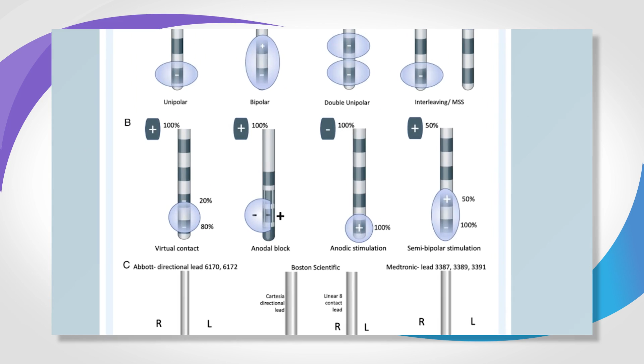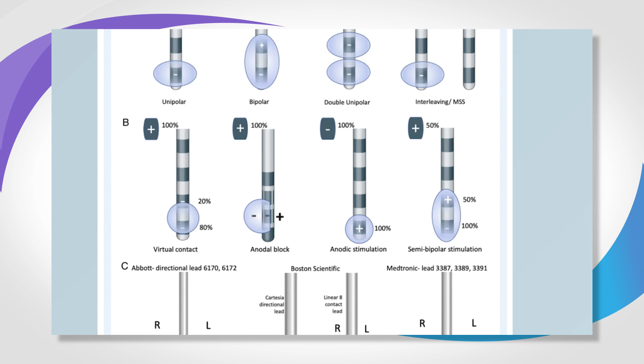and the bottom contact on the electrode itself is positive. This is not used very often, but it's an option to you as a programmer. And in the semi-bipolar stimulation, we see a negative contact on the bottom of the electrode, and there are two positives, so 50% at the battery and 50% on the electrode adjacent to the negative contact.